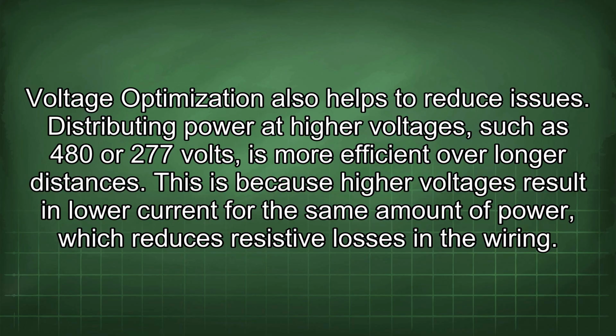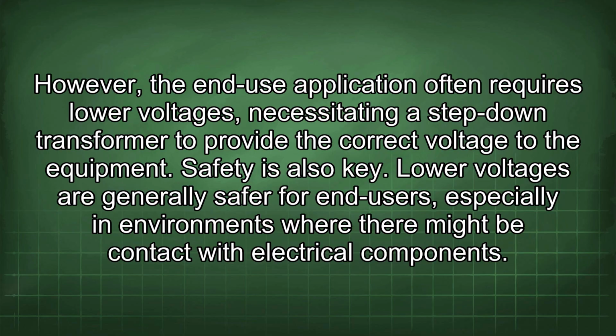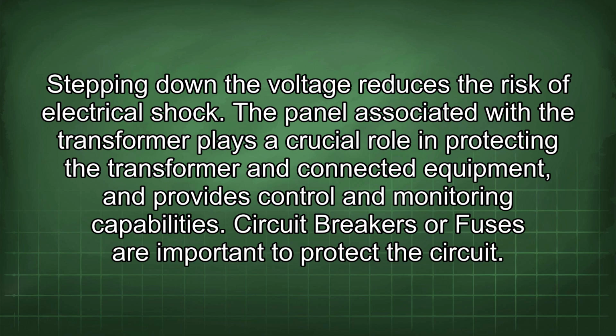Voltage optimization also helps to reduce issues. Distributing power at higher voltages, such as 480 or 277 volts, is more efficient over longer distances. This is because higher voltages result in lower current for the same amount of power, which reduces resistive losses in the wiring. However, the end-use application often requires lower voltages, necessitating a step-down transformer to provide the correct voltage to the equipment. Safety is also key. Lower voltages are generally safer for end users, especially in environments where there might be contact with the electrical components. Stepping down the voltage reduces the risk of electrical shock.